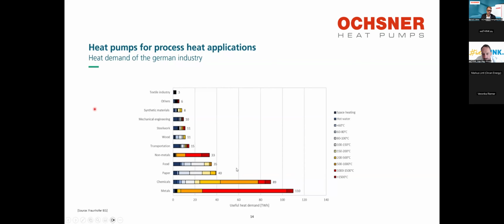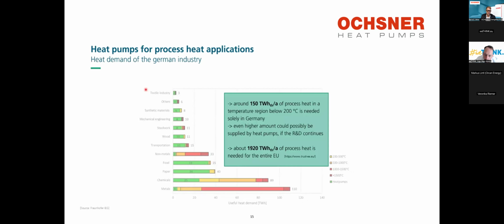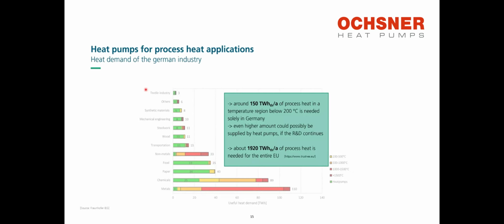And as you can see, until the yellow one, you go up to 200 degrees C of demand of temperature. So the chemicals and the metals have much higher temperatures, but there are around 150 terawatt hours thermal power per year of process heat in the temperature region below 200 degrees C. And this is a study only for the German industry. So when we're looking over all Europe, it's even much higher. As you can see, it's 1,920 in this area needed in the entire European Union. But you can see it's a very big opportunity for process heat pumps, where we are almost already there.